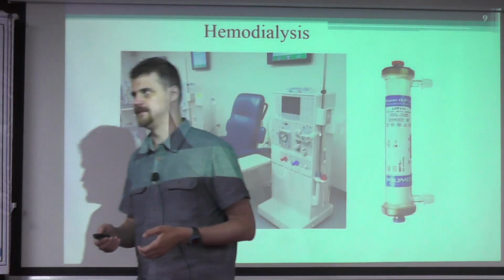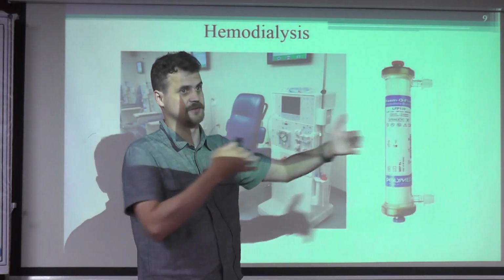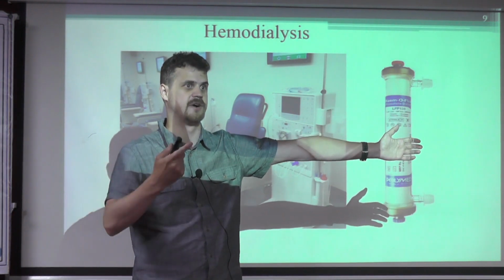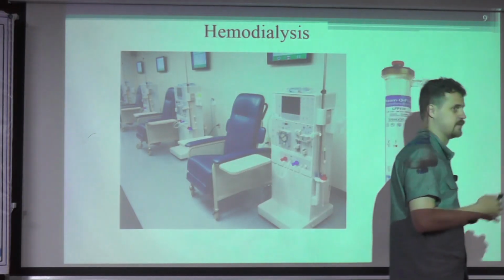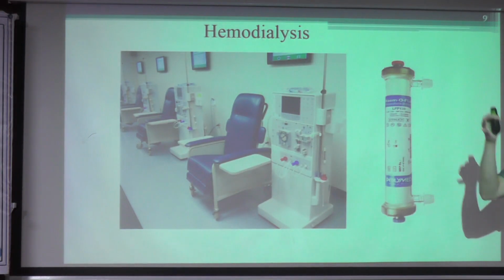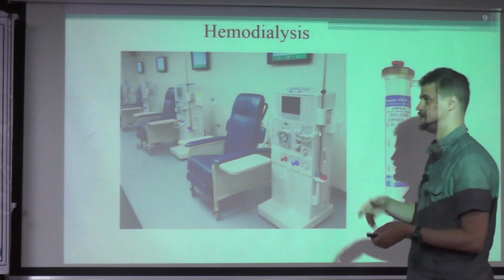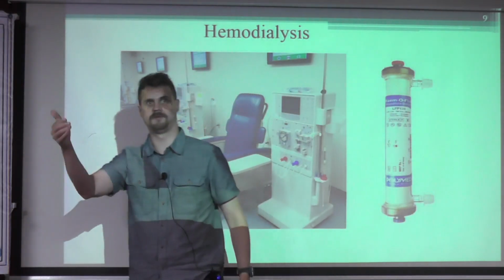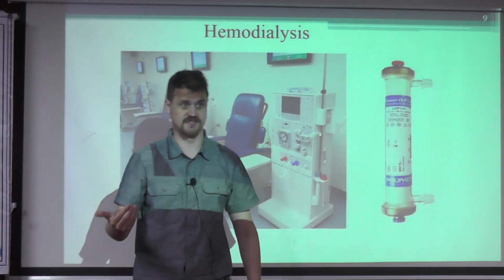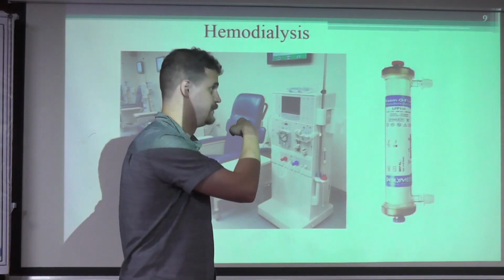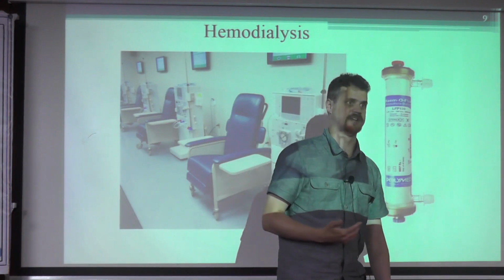And basically, for one procedure, we'll have to spend even more water to prepare this amount of dialysis solution that we can use for one patient for one procedure. And of course, these hemodialysis centers require a specific room where we can establish the filters of reverse osmosis, where we should use the carbon filters and other types of filters that can prepare the water that will actually meet the requirements for the procedure of hemodialysis, because even a small contamination of water can affect the quality of dialysis solution.